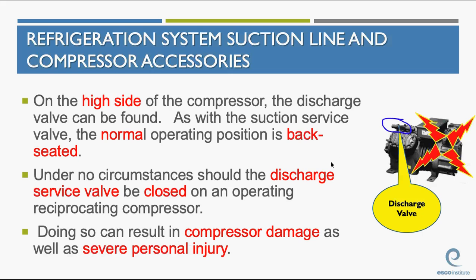Okay, for those of you who I worked with in the shop in York, when we were looking at that big semi-hermetic three-phase compressor for the 6-door reach-in, the supermarket reach-in that's in the middle of your shop, one of the things I did before we powered it, I personally went and checked to make sure that discharge valve was open. Okay, you don't operate a compressor with the discharge valve closed.